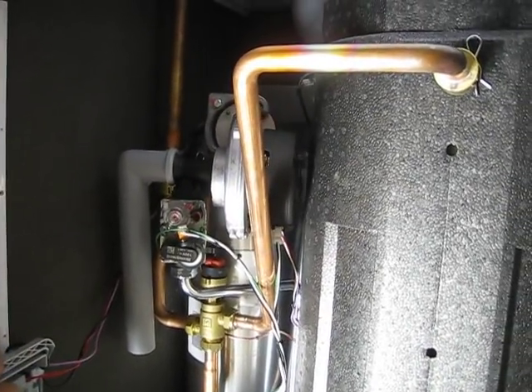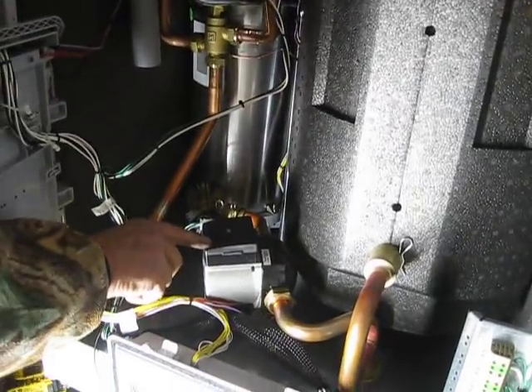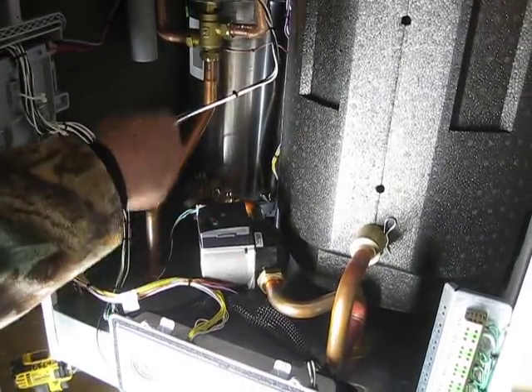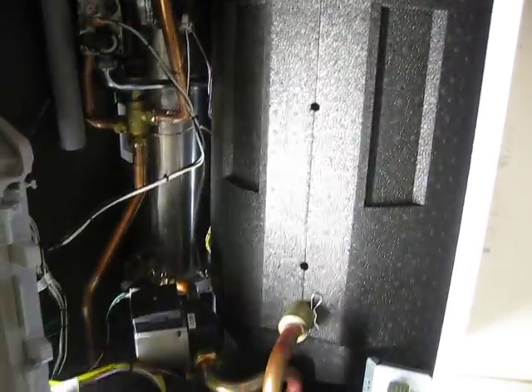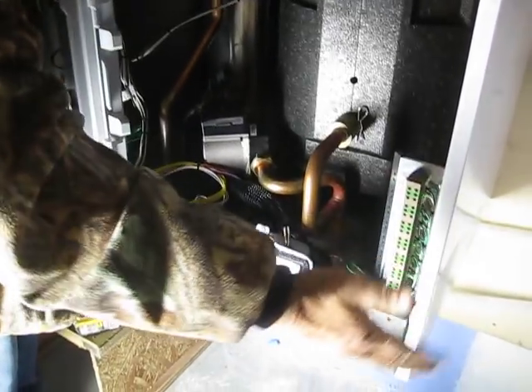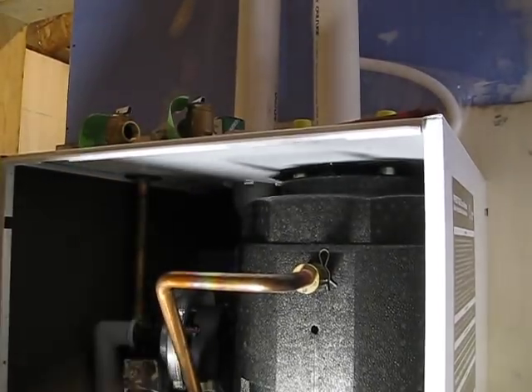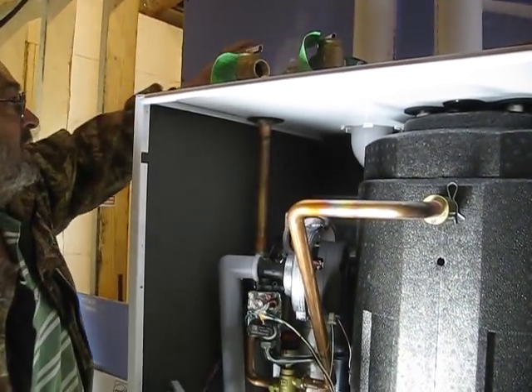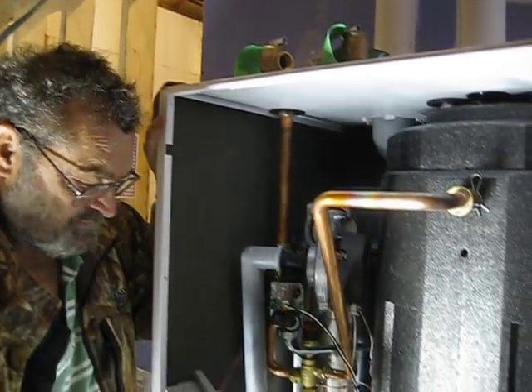And this is the burner assembly and blower. This is the brain box. This is a circulating pump that circulates the water throughout the system. The domestic hot water comes from this 14-gallon tank out the top. And the hot water for the baseboard comes out the bottom for the floor. It's 120 degrees. This water here will be about 160, 180. And it'll come back, and then we'll have a mixer valve on there so you can adjust it so you don't scald anyone.